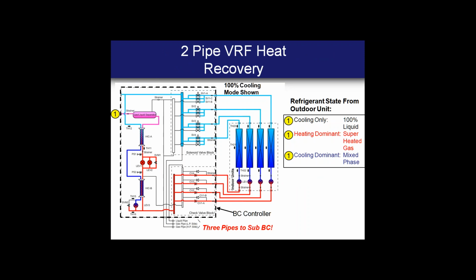We're not going to spend a lot of time talking about this, but I want you to be aware of it and just know that there are additional tools available that can help walk through the refrigeration flow diagram in greater detail. The important thing to keep in mind is you're dealing with those three states of refrigerant. And again, when you're in a heat recovery mode, specifically the cooling dominant mode, what you'll actually see from the outdoor unit is a mixed phase refrigerant coming into that gas liquid separator at point 1. And again, that's what separates off those two states and feeds the hot gas to the indoor units in heat, and then medium pressure subcooled liquid to the indoor units in cool.